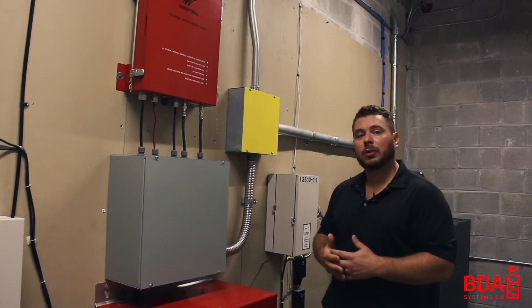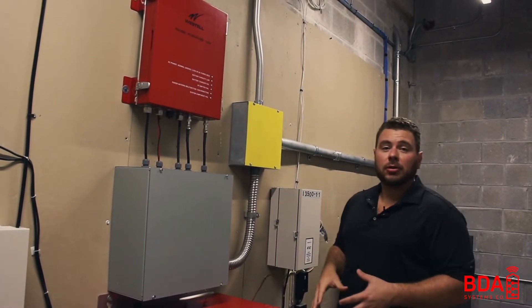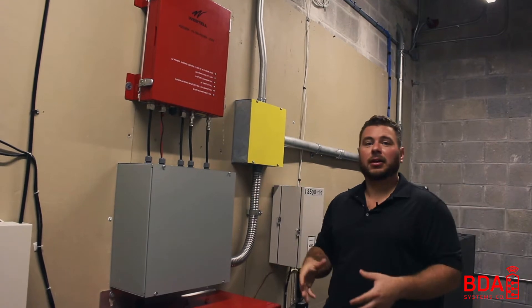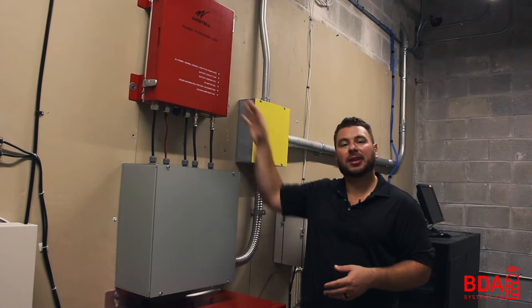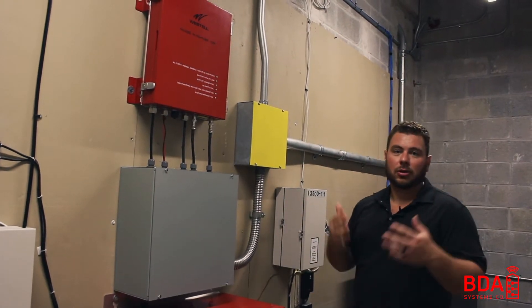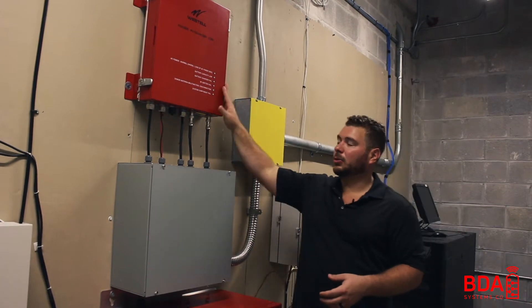This room is two-hour rated per NFPA and IFC regulations. In the event of an emergency, this building can be on fire — this room will last at least two hours. On top of that, all equipment is in a NEMA 4 enclosure, so a firefighter can come in here and spray this with a water hose and the system will still keep running.